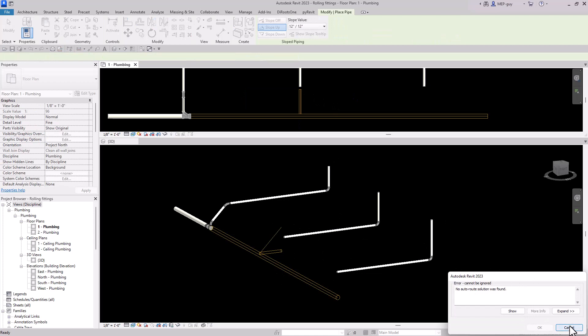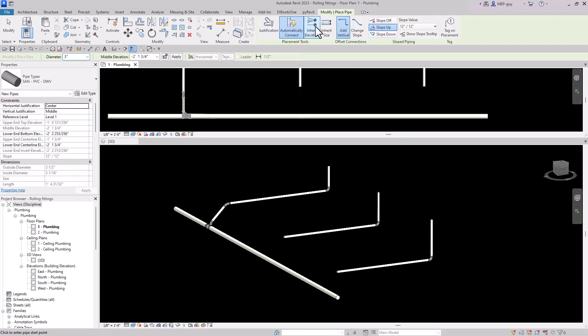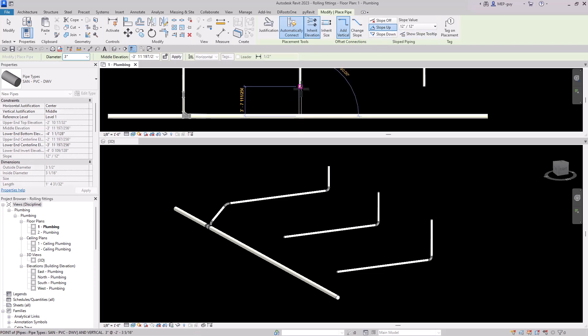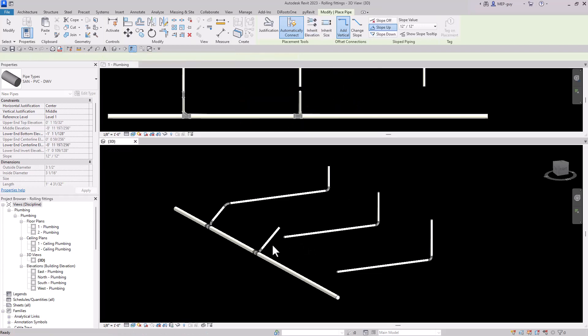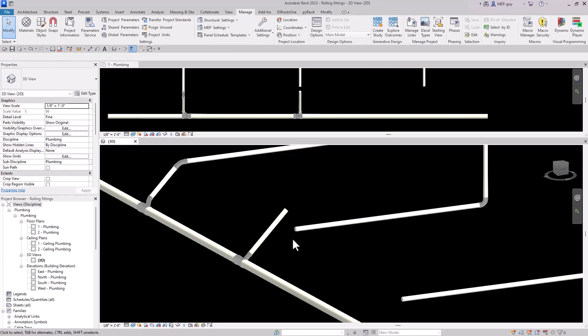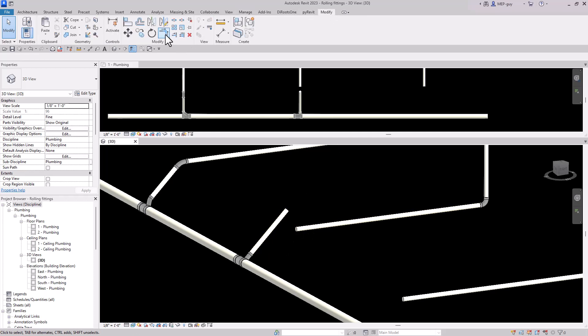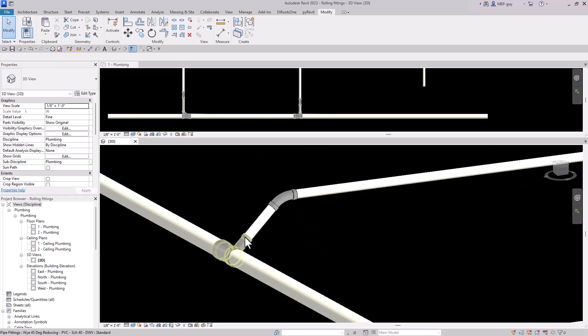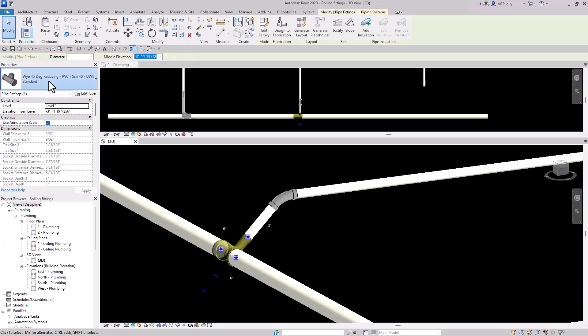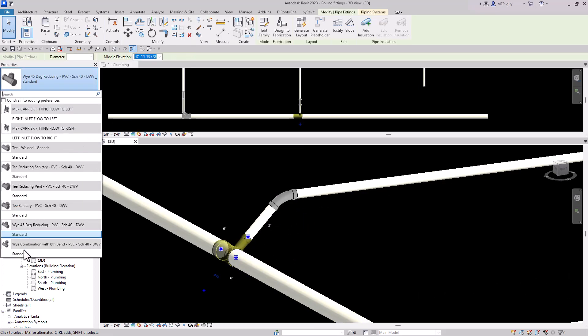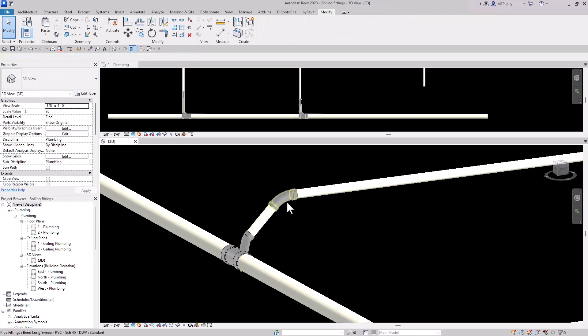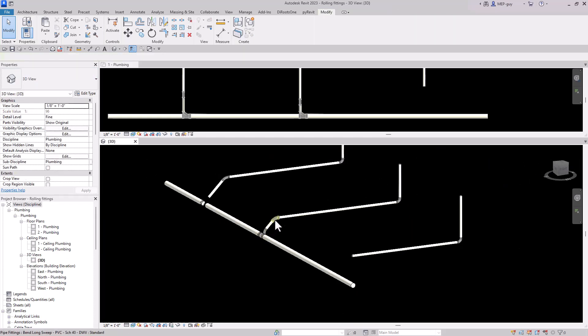Starting from the middle point of the pipe and going up, Revit will draw a perfect 45 degree angle. From there, all we have to do is use the Trim command — trim from here to here. That looks great. Then change this fitting to a Y combination fitting, and now we have a nice perfect rolling pipe. Any display artifact you see is just a graphics thing — select it and hit Escape, it won't cause any issues.